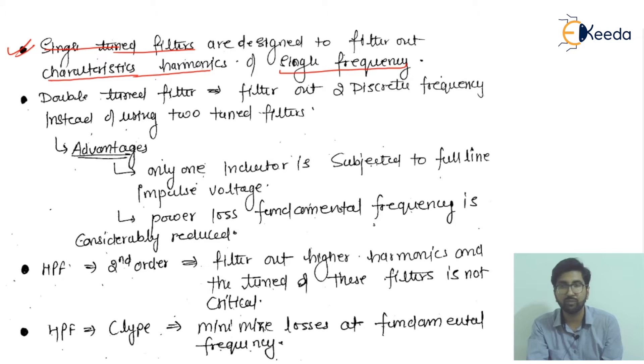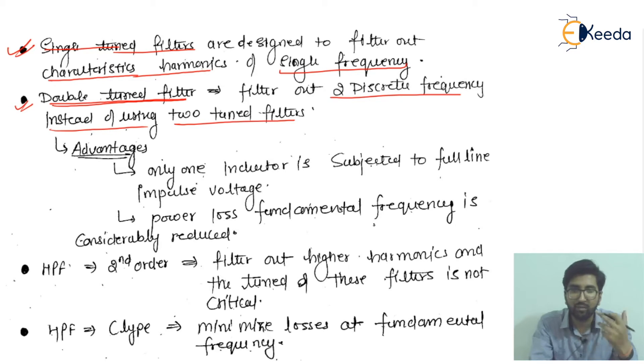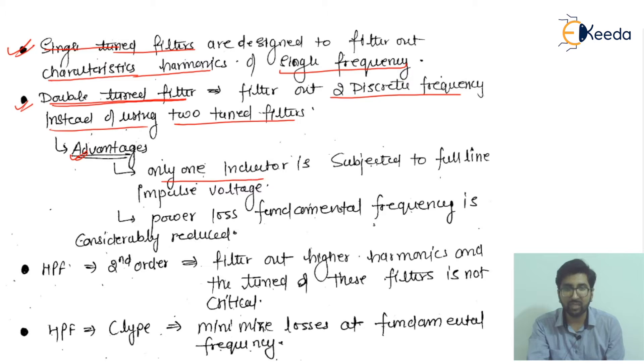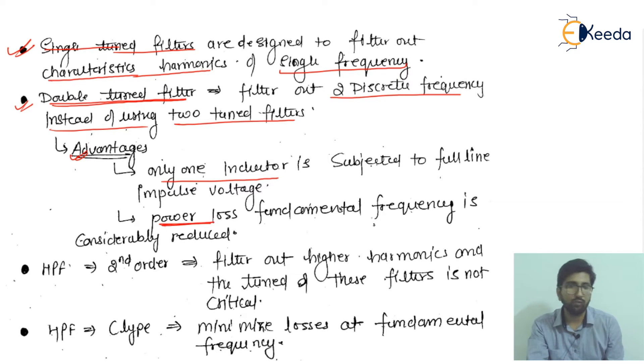The double tuned filter is designed to filter out two discrete frequencies, instead of using two separate single tuned filters. An advantage of the double tuned filter is that only one inductor is subject to the full line impulse voltage. Additionally, the power loss at the fundamental frequency is considerably reduced compared to using two single tuned filters.